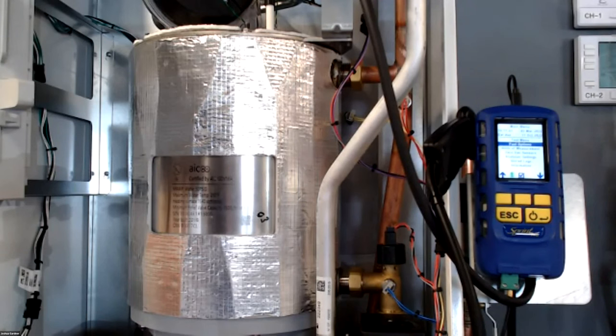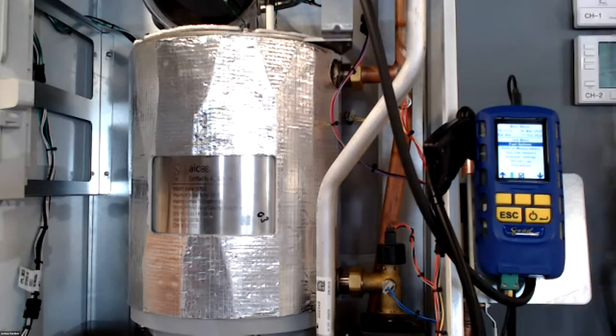We do have a natural gas pipe sizing chart in the book for black iron. So that gives you guys a little bit of help, but the code book, definitely refer to that, because we see this problem a lot with CSST. Had one last night where they're dropping 5 inches. So we want to watch out for that on the gas valve. Going down to the flow sensor, we looked at that.